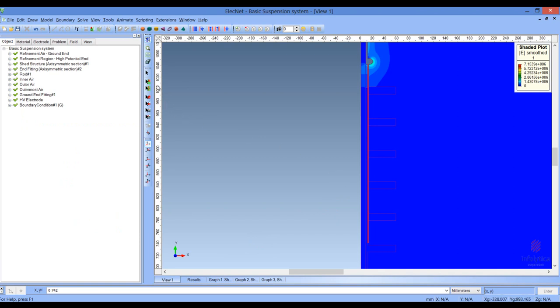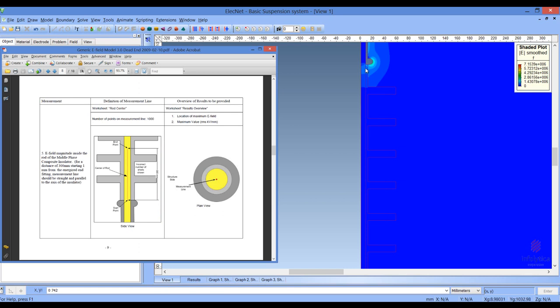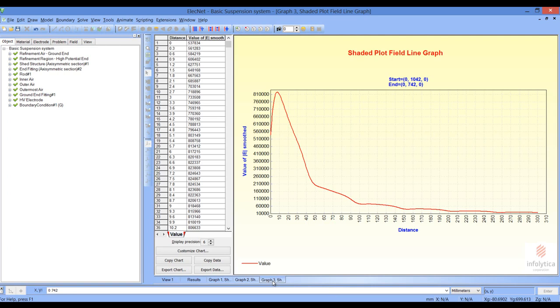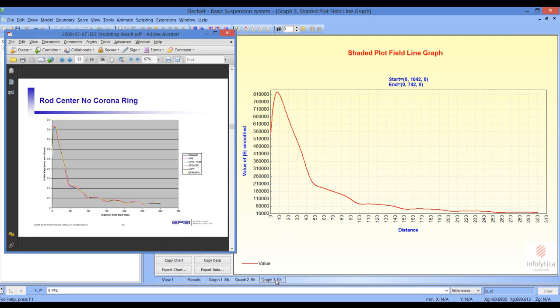Let's look at the final contour now. The last contour is taken along the rod center, as shown in the description in the EPRI document. Let's display that contour in our solution view. It starts at the end of the fitting and goes down 300 mm down the rod center. The result of the electric stress along that contour is shown in the following chart. Comparing again to the EPRI document, you can see that the shape and values are comparable.